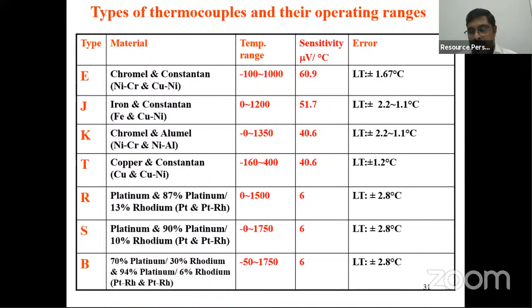And then the chromel-type thermocouple is very highly sensitive. But the problem with the E-type thermocouple is it needs periodic calibration. And R, S and B type thermocouples are very expensive. If you are going for temperature measurement above 1000 degrees Celsius, then you prefer R, S or B type thermocouple. Okay. So here you can see whatever I have shown there.